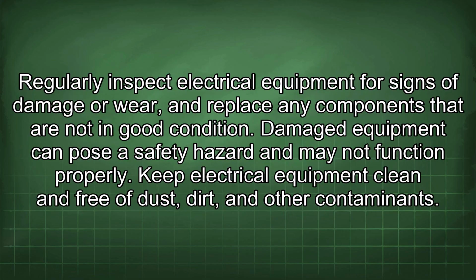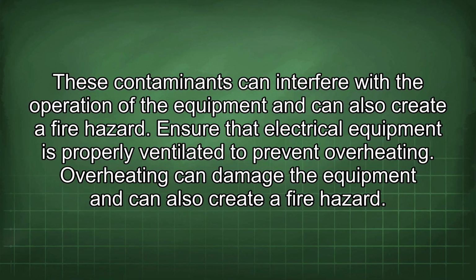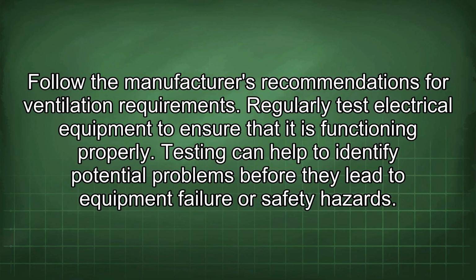Regularly inspect electrical equipment for signs of damage or wear, and replace any components that are not in good condition. Damaged equipment can pose a safety hazard and may not function properly. Keep electrical equipment clean and free of dust, dirt, and other contaminants. These contaminants can interfere with the operation of the equipment and can also create a fire hazard. Ensure that electrical equipment is properly ventilated to prevent overheating. Overheating can damage the equipment and can also create a fire hazard. Follow the manufacturer's recommendations for ventilation requirements.